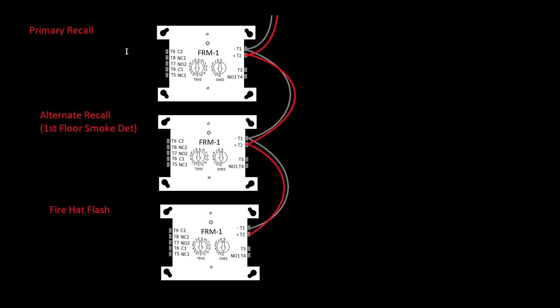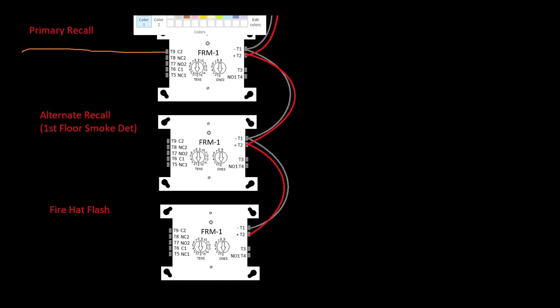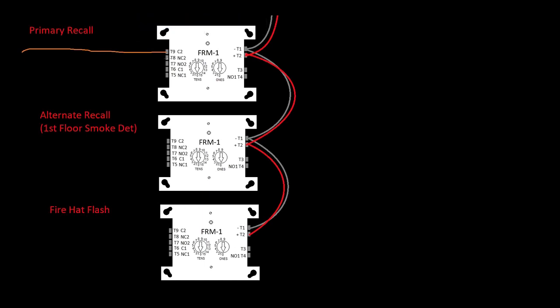Now we're going to just send a bunch of wires into the controller if you're installing a new system. The elevator guy will have to tell you whether or not he wants a normally open wire or normally closed wire. They're definitely going to get a common and you're going to label it common. The easiest way to do it, give them three wires if you're not sure, give them all three and label them, so they got common, normally closed, and normally open.